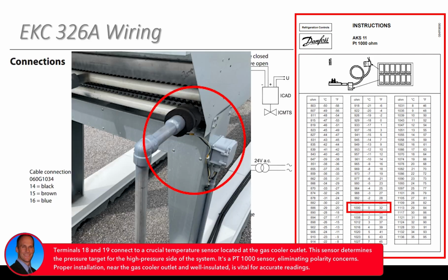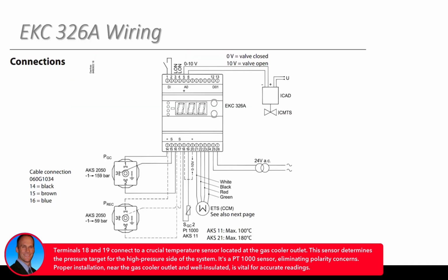It's a PT1000, so there's no polarity to worry about, which is good. But just the installation of it on the opposite end, on the pipe at the outlet of the gas cooler itself, I just go back and harp on it again, that very close to the outlet of the gas cooler and insulated are two very important parts of the installation of that sensor.